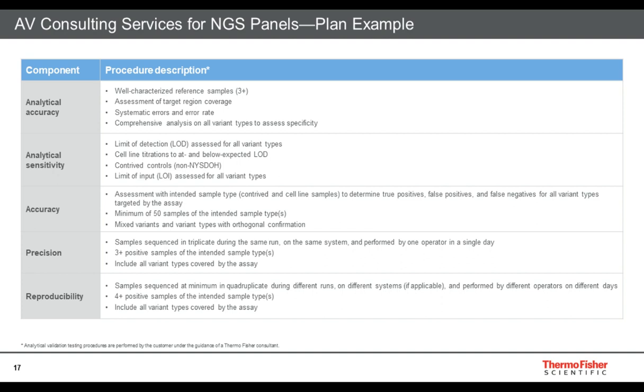We finish with reproducibility — inter-assay reproducibility. If I take a handful of samples and run them on different systems, by different operators, on different days with different barcodes, do I get the same results across all replicates? Just like precision, we want to make sure we include all variant types covered by the assay.